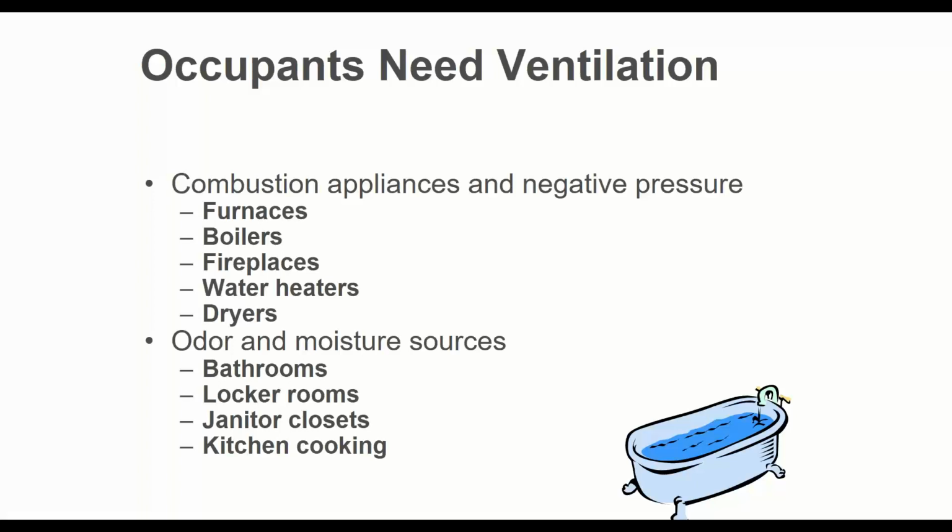What kind of exhaust air might? Bathrooms might. Locker rooms might. Kitchens, we're not going to use that exhaust air. It's going to be sticky, gooey, caustic, all that stuff. We're not going to use it from some kind of weird chemical process, things like that. But normal building exhaust, we absolutely will.